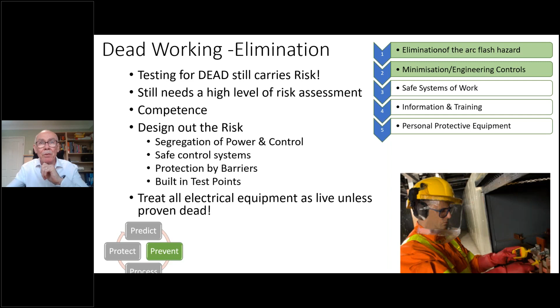Designers of electrical systems need to consider eliminating live work as part of the overall system design - installing segregation of power and control, not having them in the same panel, safe control systems, protection by barriers in place, and built-in test points for testing. But the main issue here is that we treat everything as live until it's proven dead.